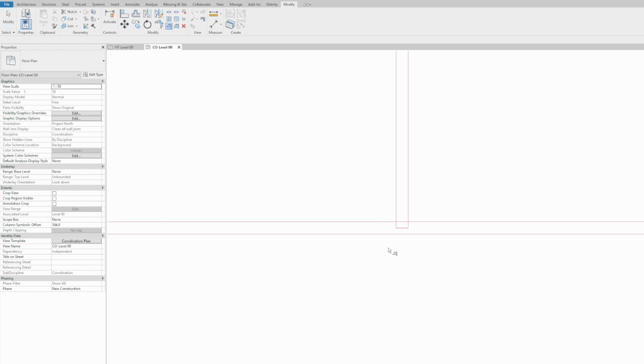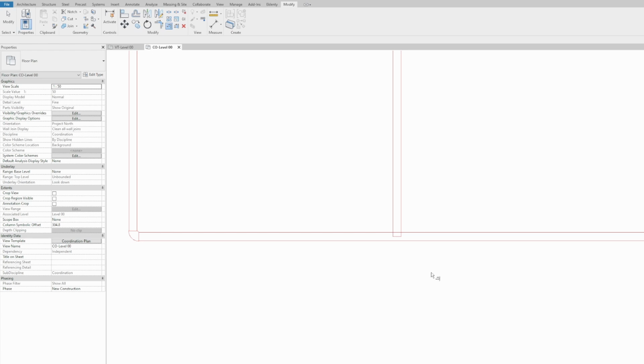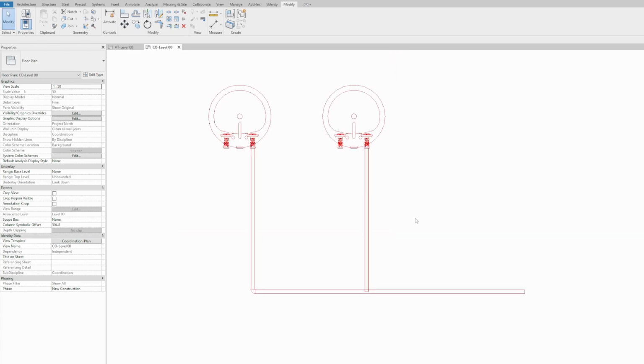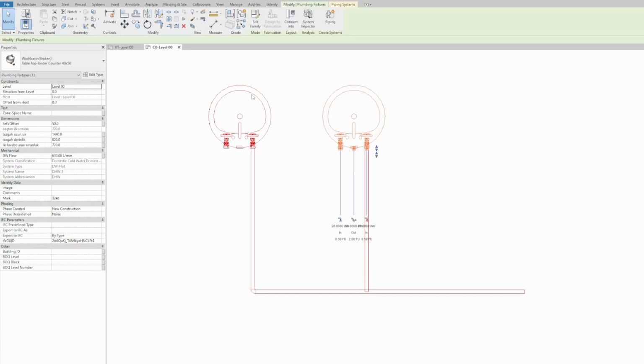As you can see, it doesn't connect. It didn't generate a tee fitting instance here, and it didn't connect. Well, these kinds of situations happen during design, right? And when they happen, they make you say, okay, Revit is acting weird today again. But actually, these kinds of inconveniences have reasons. Let's take a look at what's going on in this family.